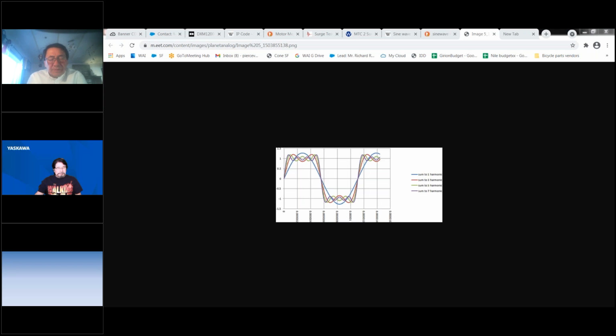Okay, so that's interesting, because even without a VFD, if you have power line harmonics, such as what you see here in this diagram, where we're not talking about a nice blue sine wave, but one of the other waveforms, you need to filter it. So in the case where the power company is causing the harmonics, even though you have a contactor, no VFD, your submersible motor could be at risk, and you're going to have to filter that input. I think what we're seeing now is that because of the change in the insulation, the inability for the motor to dissipate as much heat, because of the lower inertia, which makes the motor much more vulnerable to harmonics or aberrations on the sine wave, the motors need sine waves. And there's a lot of data now that's telling us that this is the case.